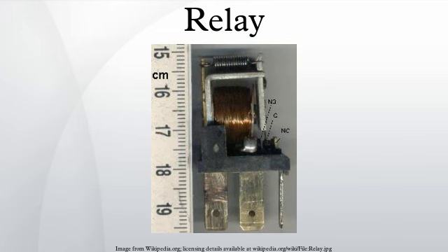Reed relays can switch faster than larger relays and require very little power from the control circuit. However, they have relatively low switching current and voltage ratings. Though rare, the reeds can become magnetized over time, which makes them stick on even when no current is present. Changing the orientation of the reeds with respect to the solenoid's magnetic field can resolve this problem. Sealed contacts with mercury-wetted contacts have longer operating lives and less contact chatter than any other kind of relay.